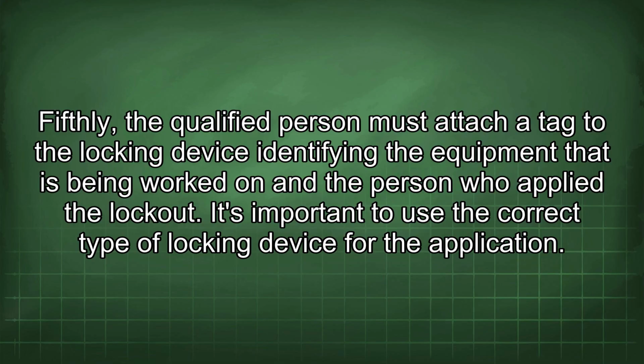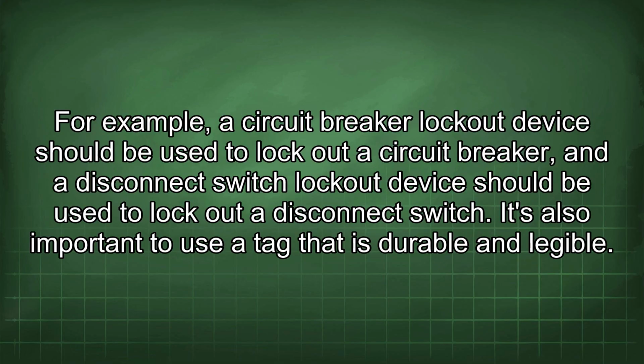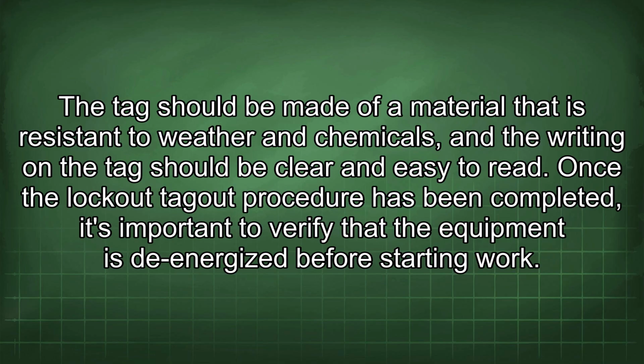It's important to use the correct type of locking device for the application. For example, a circuit breaker lockout device should be used to lock out a circuit breaker, and a disconnect switch lockout device should be used to lock out a disconnect switch. It's also important to use a tag that is durable and legible. The tag should be made of a material that is resistant to weather and chemicals, and the writing on the tag should be clear and easy to read.